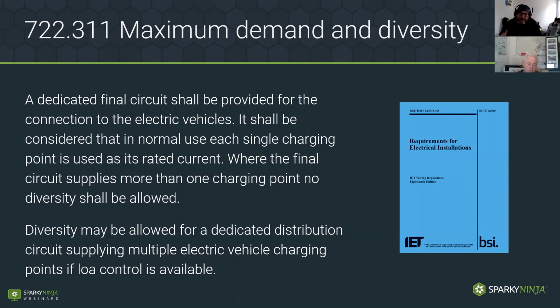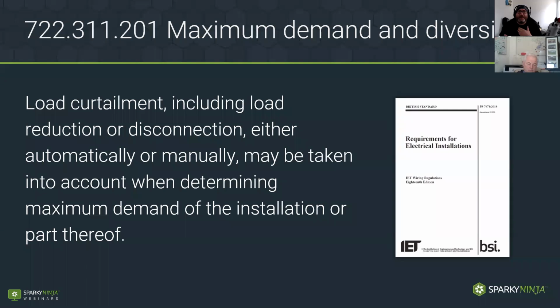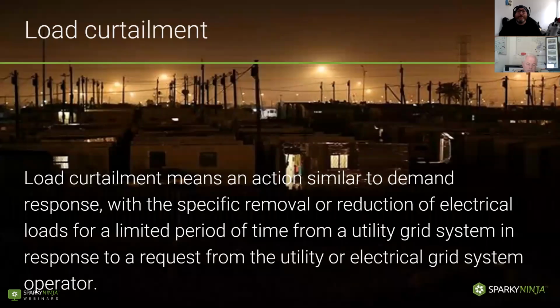This has been rewritten in very simple terms now, which basically says load curtailment, including load reduction or disconnection, either automatically or manually, may be taken into account when determining maximum demand on the installation or part thereof. This is heavily relying on communication with the control equipment. To summarize curtailment, this is an action similar to demand response, with the specific removal or reduction of electrical loads for limited periods of time for the utility grid system to request you to take less, so allow the grid to actually operate.